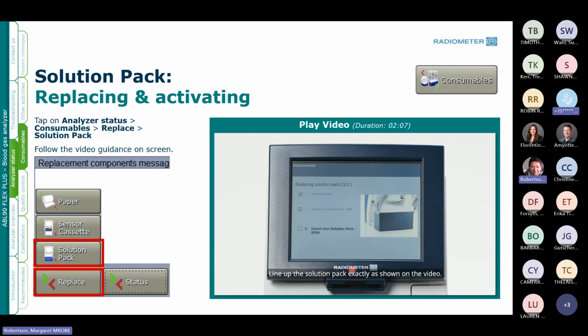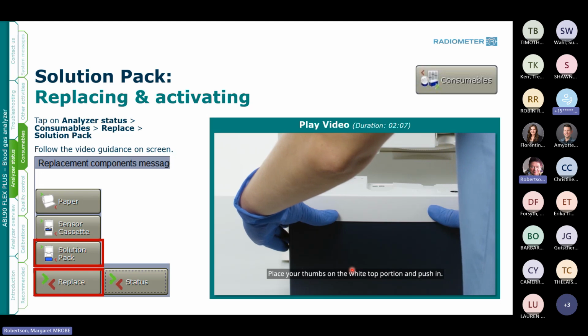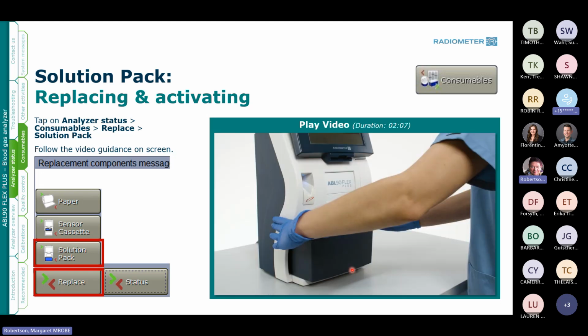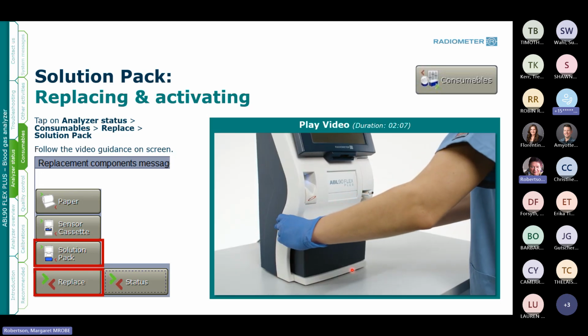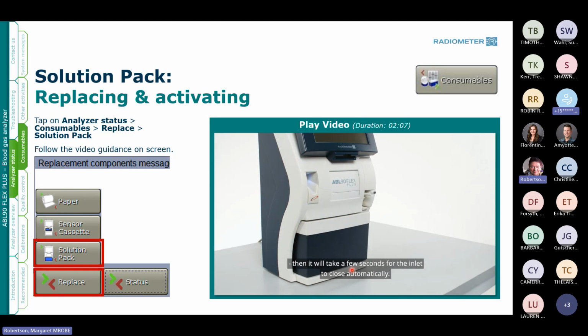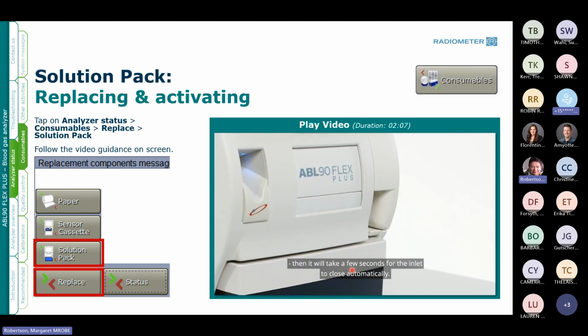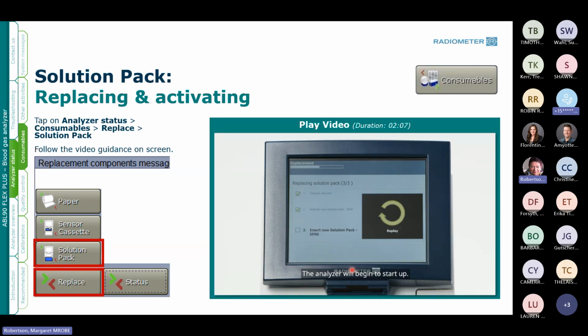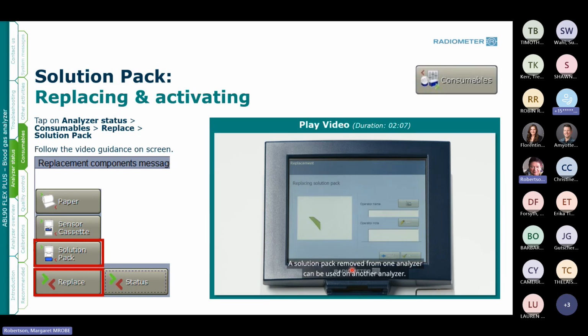Line up the solution pack exactly as shown on the video. Place your thumbs on the white top portion and push in. You're going to hear a click. Then it will take a few seconds for the inlet to close automatically. The analyzer will begin to start up. A solution pack removed from one analyzer can be used on another analyzer.